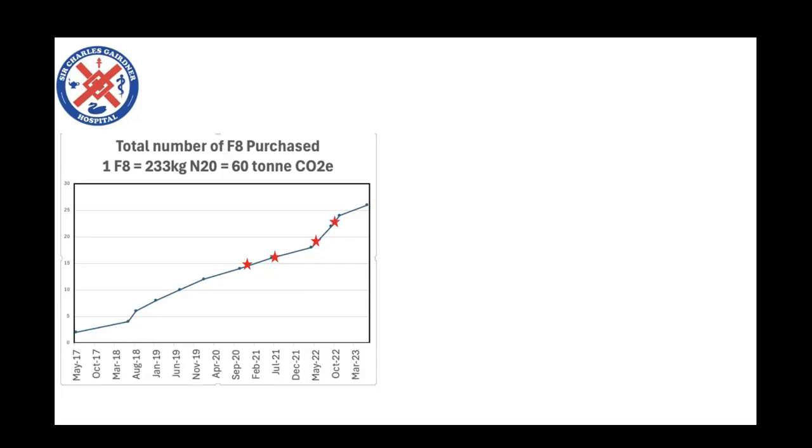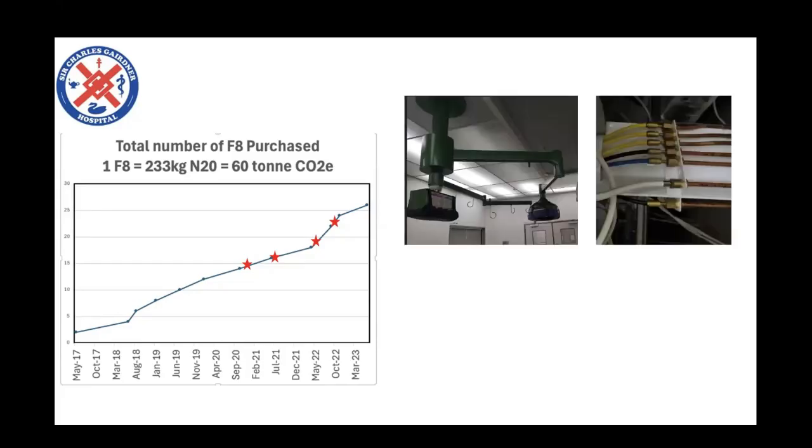And it wasn't until we got the next data point that we could tell that not only was there a big leak, the leak had actually doubled. And so now we're up to about 2 litres a minute being lost. At which stage I got a new engineer helping us, and we started finding things. The first thing was at least, and I say it's at least, 6 of our pendant systems were seriously leaking.